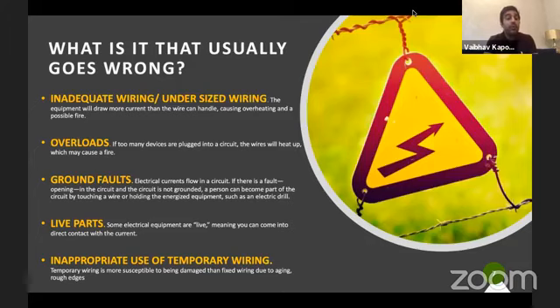Last point, inappropriate use of temporary wiring. Again, temporary wiring is more susceptible to damage than fixed due to aging. We do a lot of outdoor shows, and most of the time our wiring is exposed to harsh weather conditions, let it be rain or sun. Ultimately, after a period of time, PVC cables tend to crack. So aging is a very big factor when it comes to this.